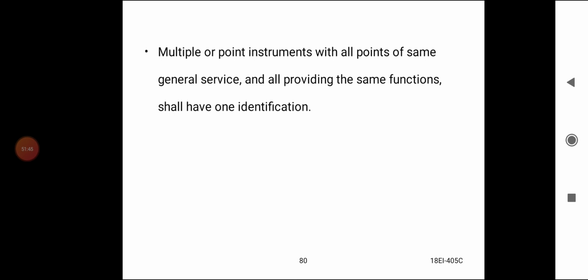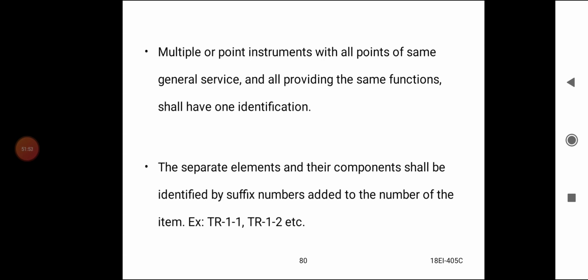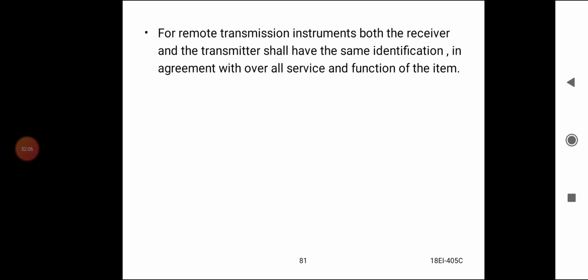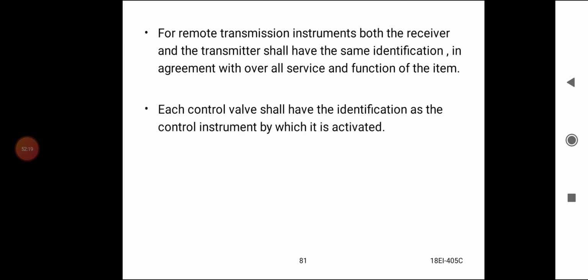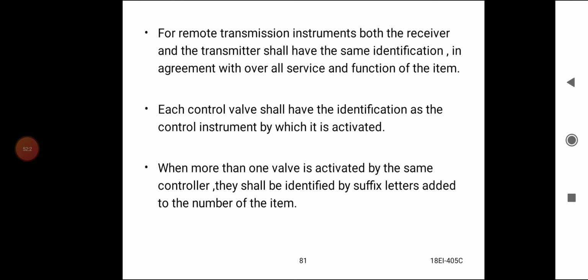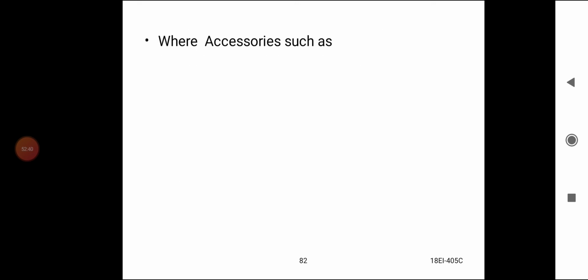Multiple point meters with all points of the same general service and all providing the same functions shall have one identification. So separate elements and their components shall be identified by suffix numbers added to the number of the item. Example: TR1-1 and TR1-2, etc. For remote transmission instruments, both receiver and transmitter shall have the same identification in agreement with the overall service and function of the item. Each control valve shall have the same identification as the control instrument by which it is activated. When more than one valve is activated by the same controller, they shall be identified by suffix letters added to the number of the item: TRC1A, TRC1B, etc. Where accessories such as valve positioners, air sets, switches, relays, etc.